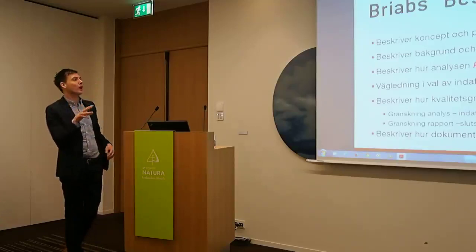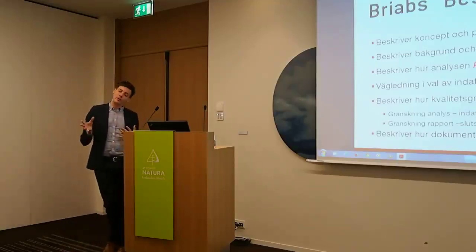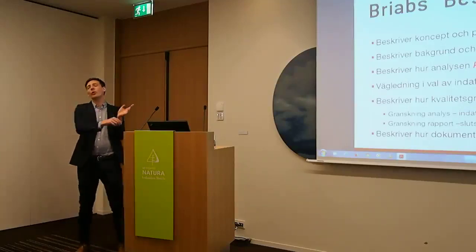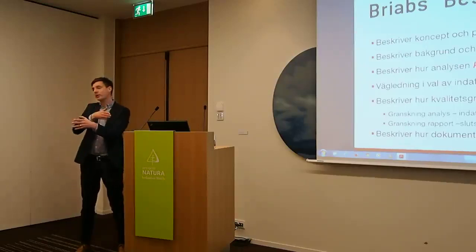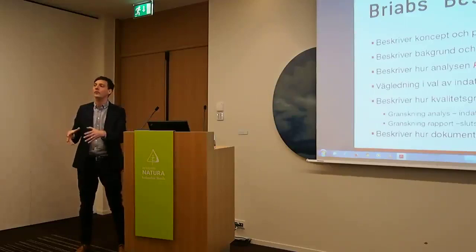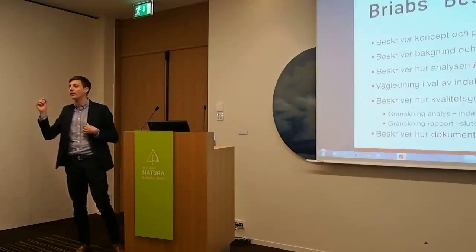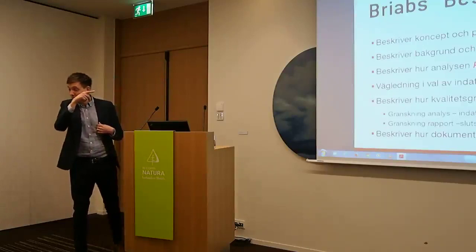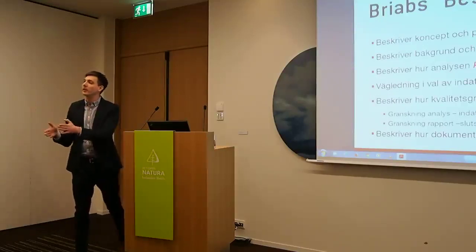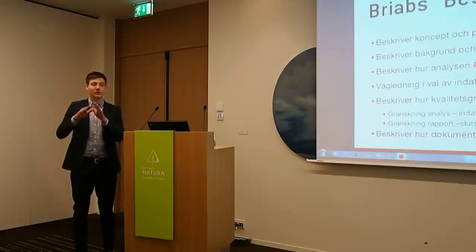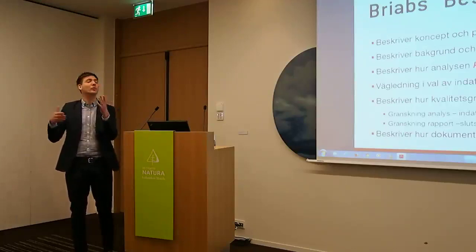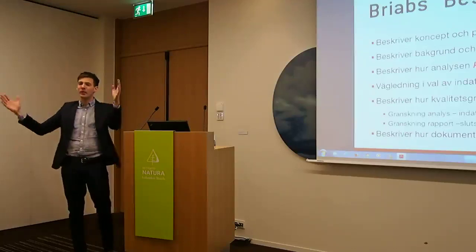And then we describe our auditing system, done in sub-parts. Before you start the calculation, you have to have a quality check to ensure that the problem is correctly defined and you have chosen the right kind of program to use. When you've done that, you have a quality check that all the input parameters in your model are correct, in line with the guidance. And if it's in line with the guidance, it will be in line with the Swedish regulations. And when you've done your simulations, your calculations, you have a quality check that the result is okay. There are no extreme values. The values are around the median, what you could expect, and you can benchmark against hand calculations to see at what level you get this result.